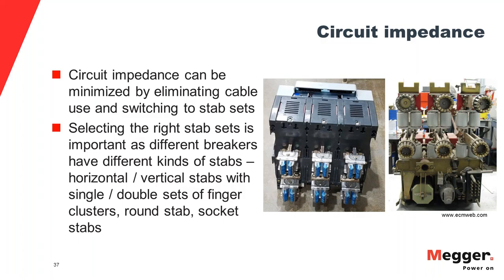They can have vertical stabs, they can have horizontal stabs, the stabs can have a single set of finger clusters or double sets of finger clusters, they can be round stabs or socket stabs. So having the right stab set for the range of breakers that you have can be a bit of a problem.